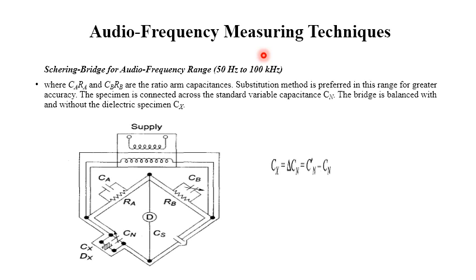Also, in order to take care of all these effects, there is a modified Schering bridge arrangement, which we can see here in this figure. This is the bridge for the audio frequency range from 50 hertz to 100 kilohertz. The capacitance used for the dielectric measurement is shown here, where CA and RA and CB and RB are the ratio arm capacitances. A substitution method is preferred in this range for greater accuracy.